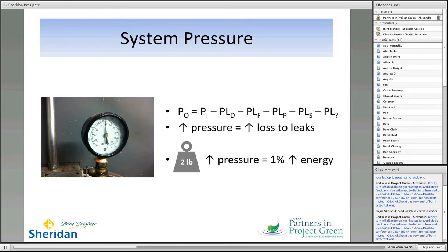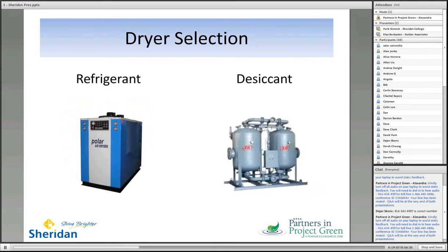The rule of thumb to apply there is that a 2-pound increase in pressure is going to increase the energy requirement of the system by 1%. If you happen to be feeding unregulated air, open-blowing leaks, you might get another 0.5 to 1% increase in energy use for every 2 pounds increase in pressure. So it's a sensitive variable and something that you can work to reduce to save energy and money.